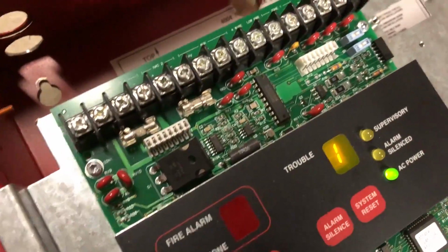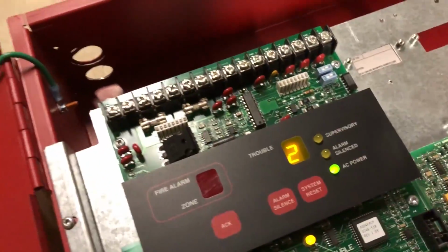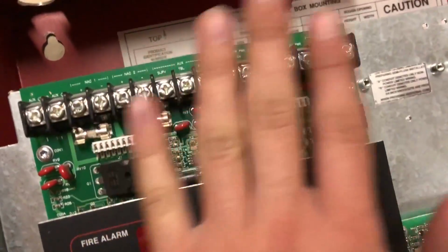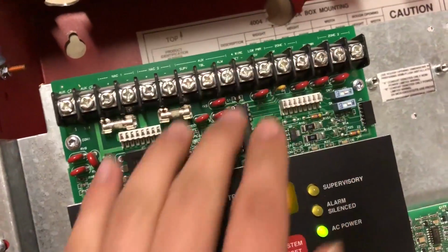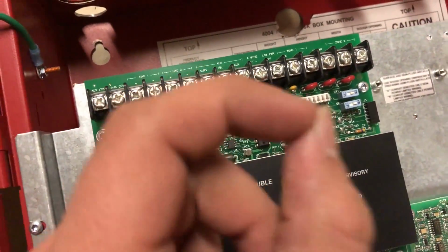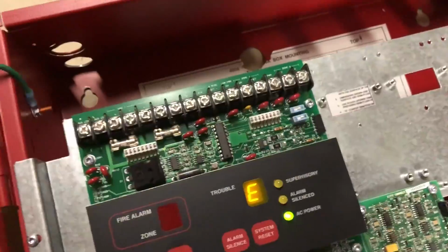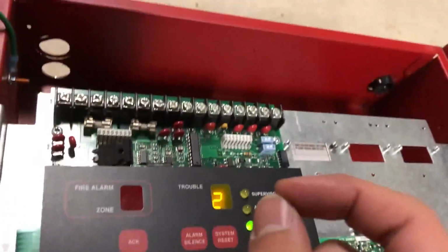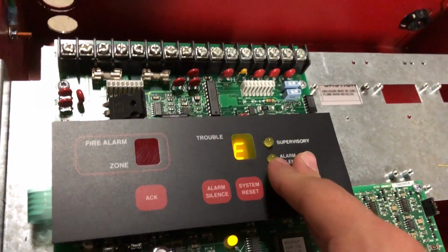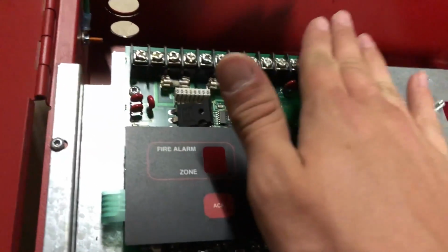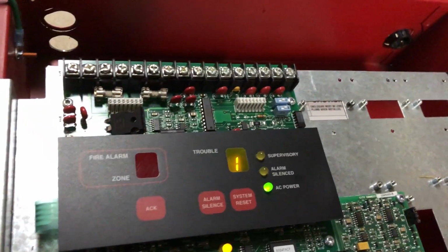resistor on anything. So what I've got here to kind of show off exactly how this works, like I said, these panels, I said they look for a short circuit, which isn't always the case. These power limited devices, or circuits, are actually looking for an increase in current. Obviously, if you were to completely short a circuit on a panel, it would actually blow up the power supply if it was non-power limited. These, of course, are all power limited.